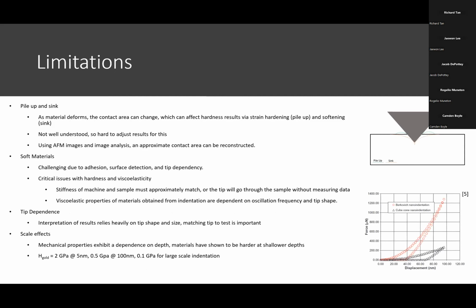And then finally, the limitations of nano indentation. So the first one is going to be something called pileup and sink. So as material deforms, the contact area can change with the tip, and this is going to affect the hardness results via strain hardening and pileup and softening and sink. The way in which this happens is not well understood, so it's hard to adjust your results for this. So the typical way that people do this is using AFM plots and image analysis. You can approximate the contact area that was present during the test.